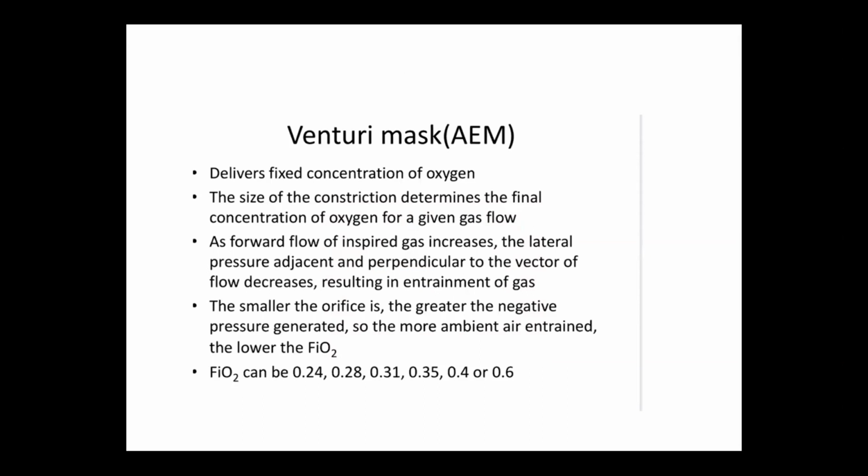The size of the valve, the size of the constriction, determines the final concentration of oxygen for a given gas flow. The next question is, on which principle does it work? It works on the Venturi principle. The Venturi principle is that if air, gas, or a liquid flows from a large orifice to a narrow orifice, the velocity increases but the pressure decreases. To compensate for that pressure, it entrains the fluid or gas, whatever it is.